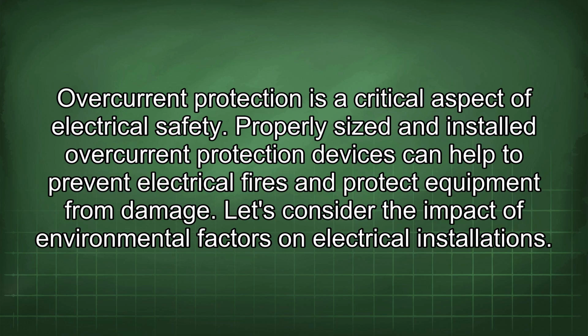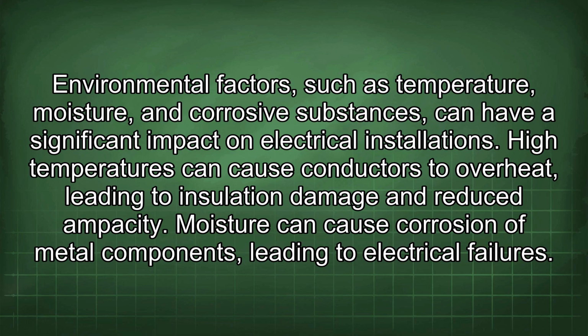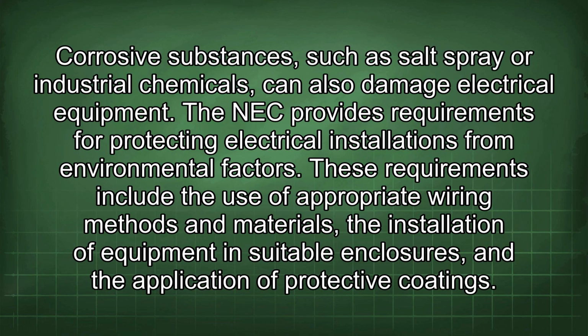Let's consider the impact of environmental factors on electrical installations. Environmental factors, such as temperature, moisture, and corrosive substances, can have a significant impact on electrical installations. High temperatures can cause conductors to overheat, leading to insulation damage and reduced ampacity. Moisture can cause corrosion of metal components, leading to electrical failures. Corrosive substances, such as salt spray or industrial chemicals, can also damage electrical equipment. The NEC provides requirements for protecting electrical installations from environmental factors.